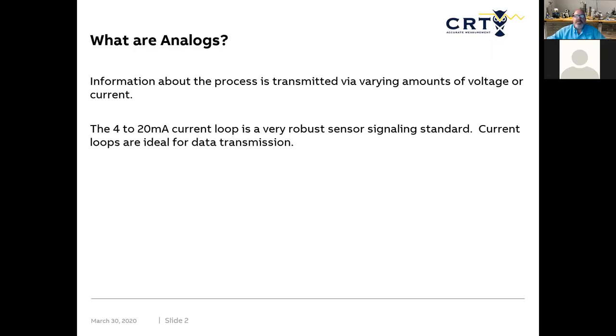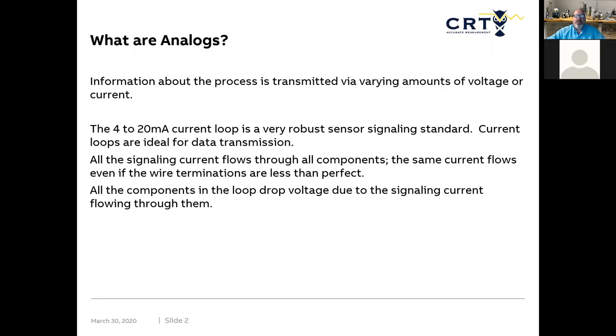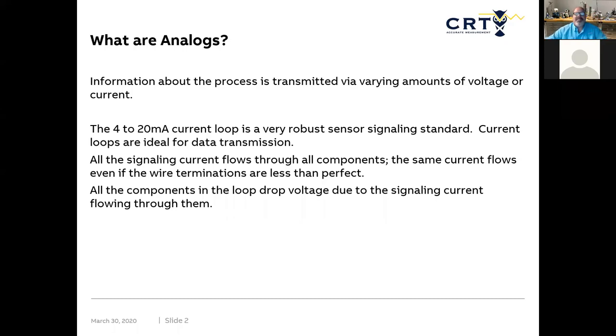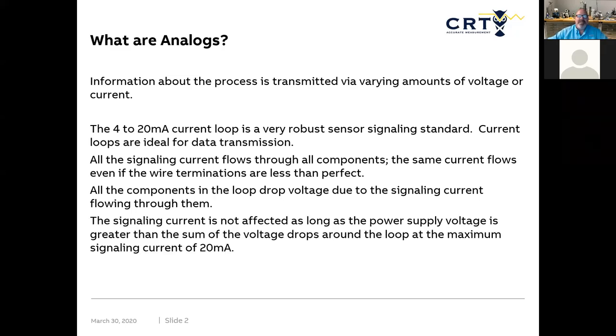The four to 20 milliamp loop is probably the most common that's out there. It's very ideal for transmissions. All the signaling current flows through all the components. All the components in the loop drop voltage due to the signaling current flowing through them. And the signaling current is not affected by the power supply voltage.